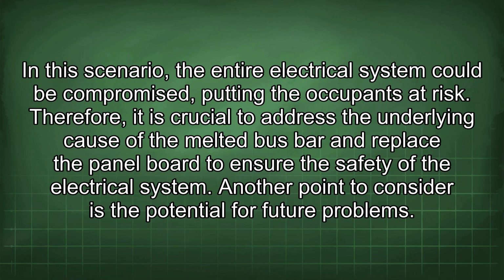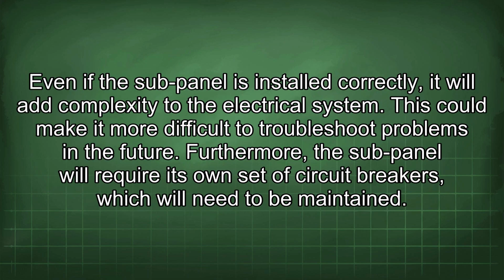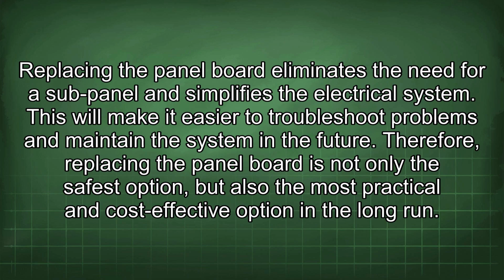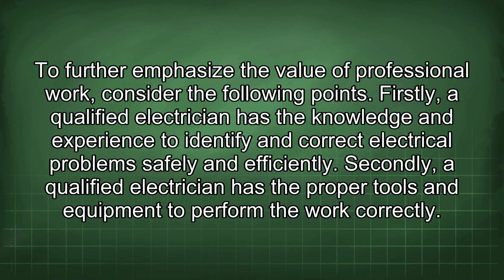Another point to consider is the potential for future problems. Even if the sub-panel is installed correctly, it will add complexity to the electrical system. This could make it more difficult to troubleshoot problems in the future. Furthermore, the sub-panel will require its own set of circuit breakers, which will need to be maintained. Replacing the panel board eliminates the need for a sub-panel and simplifies the electrical system. This will make it easier to troubleshoot problems and maintain the system in the future. Therefore, replacing the panel board is not only the safest option, but also the most practical and cost-effective option in the long run. To further emphasize the value of professional work, consider the following points.